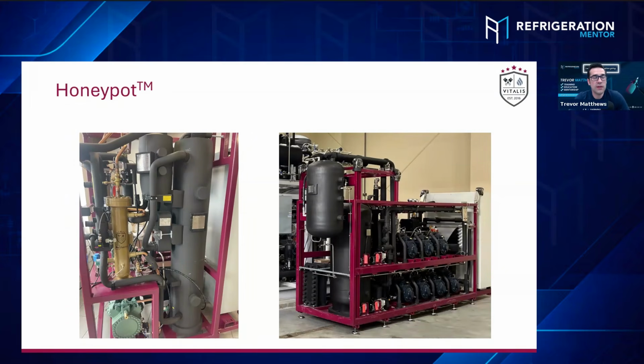Okay, great. So getting back to it, you like to add the oil when it's under vacuum. So at this point, all the valves for the oil systems are open. Is that correct? If you vacuumize the entire system, you can have all the valves open as they are in the normal operation condition. You would not have the system powerized, so there is no oil regulator active, because during the vacuum process, you don't want to powerize the system.